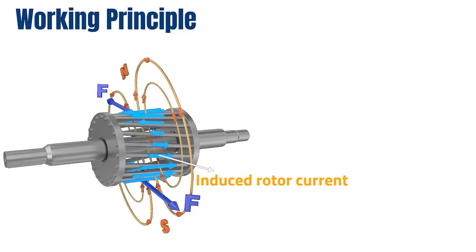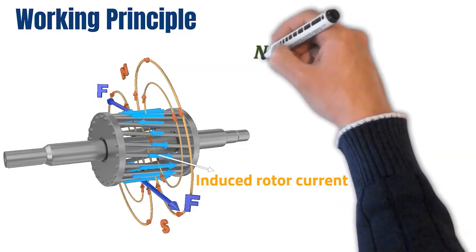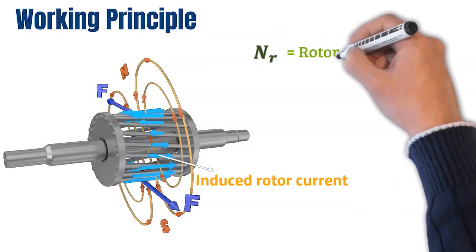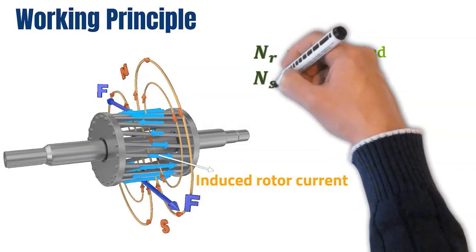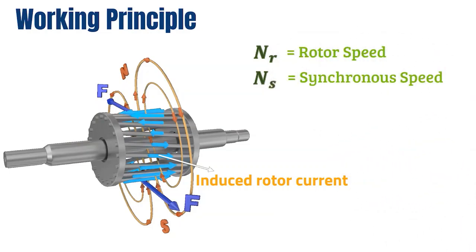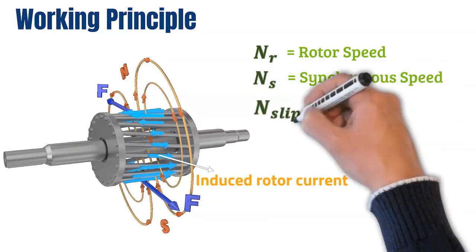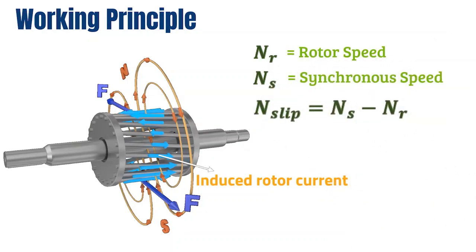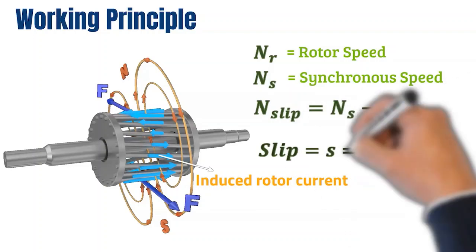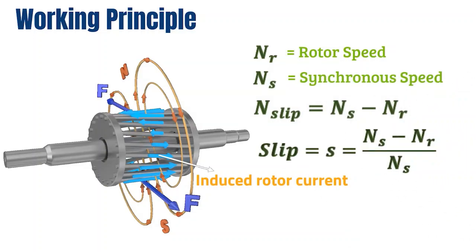One of the major observations of the induction motor is that it can never attain or exceed synchronous speed. If the rotor speed is Nr and the synchronous speed is Ns, then the speed of the magnetic field sensed by the rotor to create torque is Ns minus Nr. This is known as the slip speed. The ratio between slip speed and synchronous speed is known as slip, and the relationship between rotor speed and synchronous speed can be obtained from this.